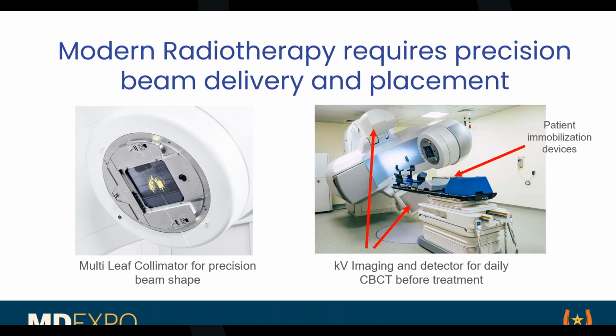Most machines will have about 120 of these little leaves that are moving around. These are parts that often fail and need to be replaced because, as you can imagine, the leaves are maybe less than a millimeter wide, there's 120 of them, and they're traveling. And so, like anything with moving parts, things break, and that's a common thing that happens. It's not a complicated fix, but it needs to be done. Otherwise, the patients can't get treated.